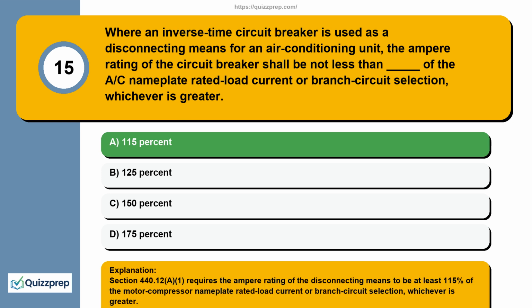Section 440.12(A)(1) requires the ampere rating of the disconnecting means to be at least 115% of the motor compressor nameplate rated load current or branch circuit selection current, whichever is greater.